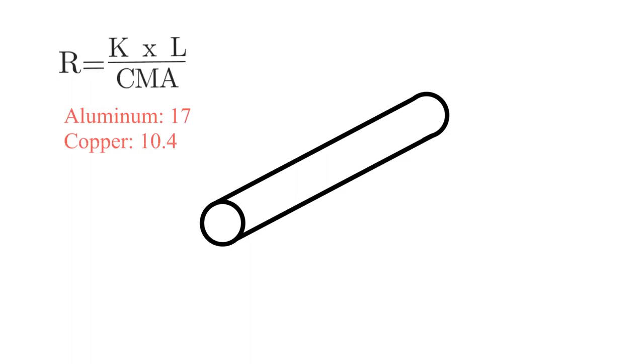So for our K, we're going to use either copper or aluminum. Those are our two most common types of conductors out there. For aluminum, that constant of resistivity is 17. For copper, it is 10.4.